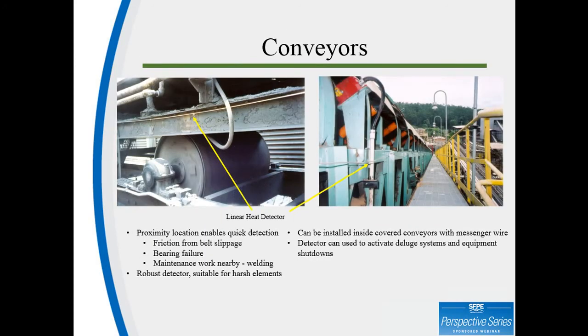Heat detection on conveyor belts is another strong application for linear heat detection. Again, the detector can be placed directly on the hazard, offering proximity detection. The primary goal of detection on conveyors is to enable quick detection for any type of operational failure. This could be a bearing failure, friction from belt slippage, a roller locks up, or anything similar. The robust design of the detector allows for an extended service life even in the harshest of environments.